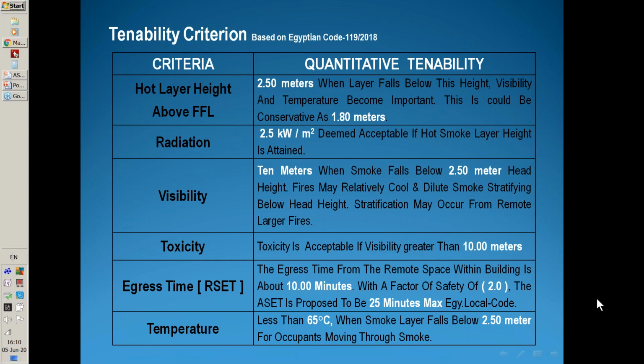Finally, we have the temperature, and the temperature of the smoke layer shall be less than 65 degrees Celsius when the smoke layer falls to 2.5 meters for occupants moving through smoke. So in any design of a smoke management system, as a technical reviewer, we ask: please show me your methodology for evacuation and your most stringent fire scenarios, and on both issues, please provide evidence that you will meet these requirements.